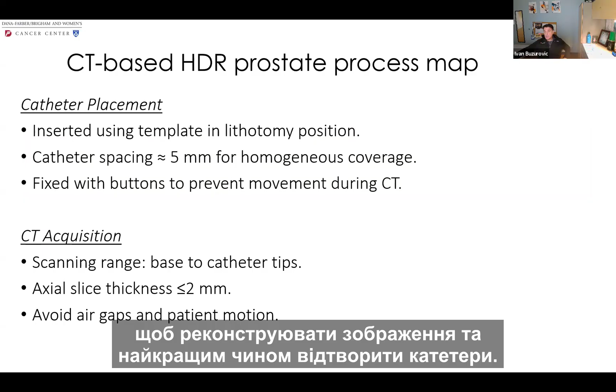Treatment planning consists of several steps. After contouring and catheter reconstruction, there is activation, normalization, optimization, measurements of the catheters as a QA, export of a treatment plan, and the treatment delivery. Catheter reconstruction in the CT is not complicated, but what is important is to go from a catheter end or a catheter tip, from a distal or proximal end, and follow those. You can see here the template and very nice and symmetric distribution of the needles.